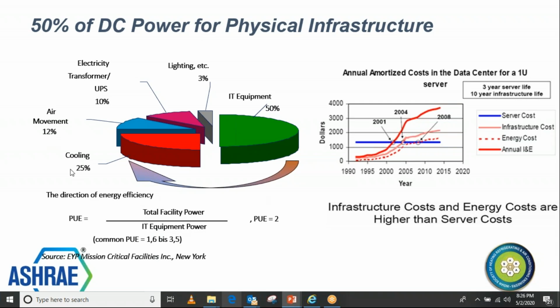Otherwise, some data centers have been designed at 1.35, 1.4 PUE. And there are many data centers in the industry at around 1.4 to 1.5 to 1.6. So 1.4 to 1.6, there are many new data centers in the last 3-4 years. And the new data centers being designed now in 2020 are all focusing below 1.5. Nobody is talking about that typically.